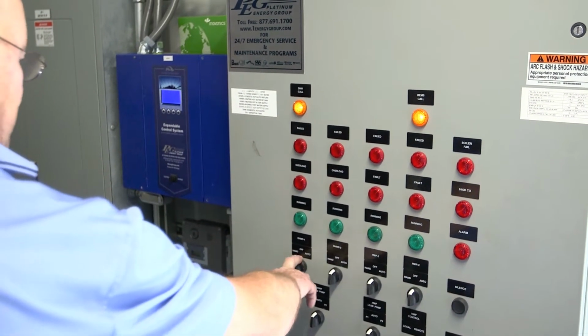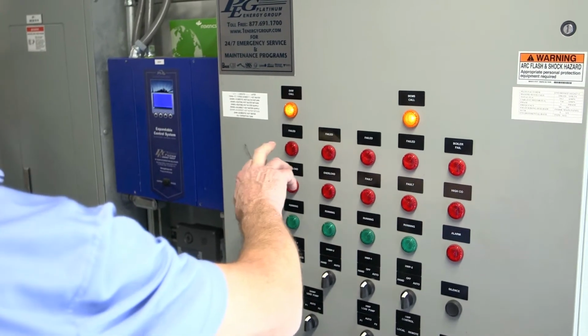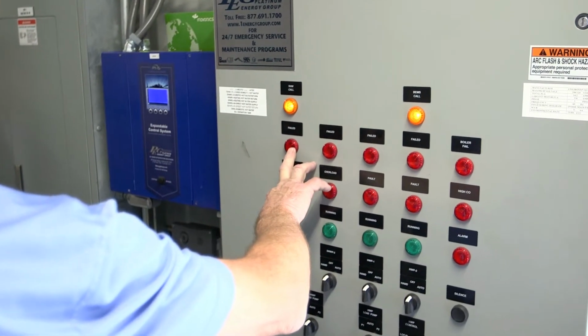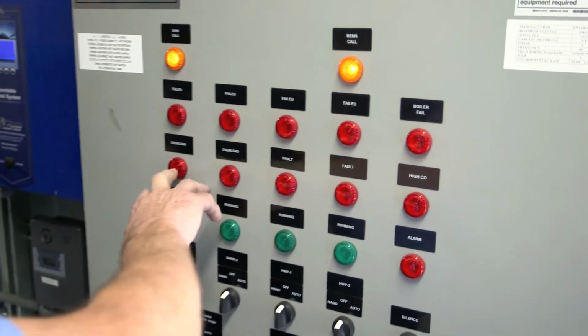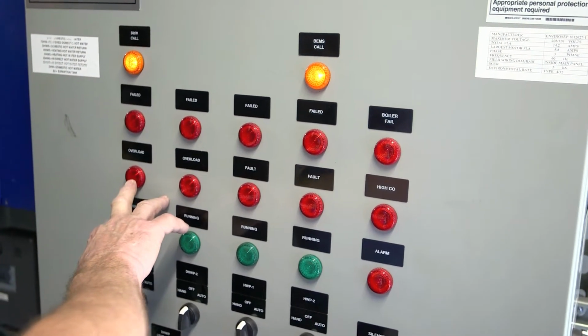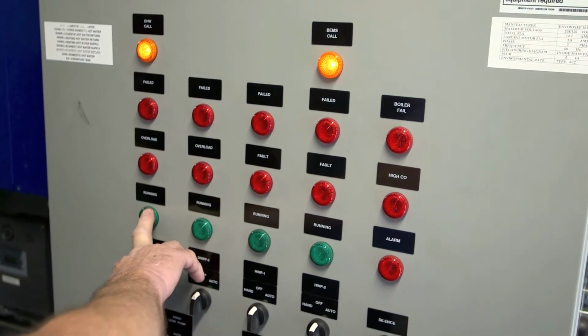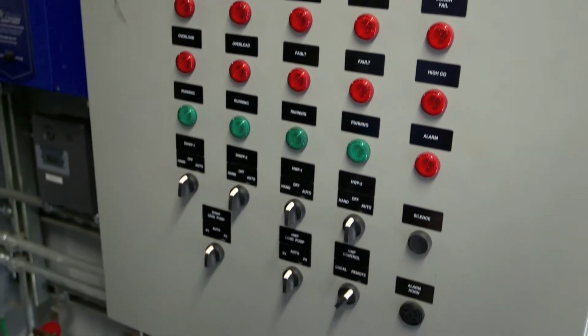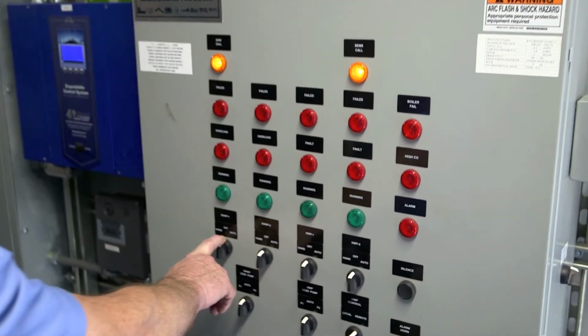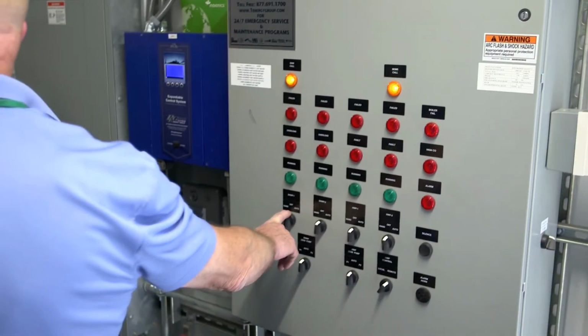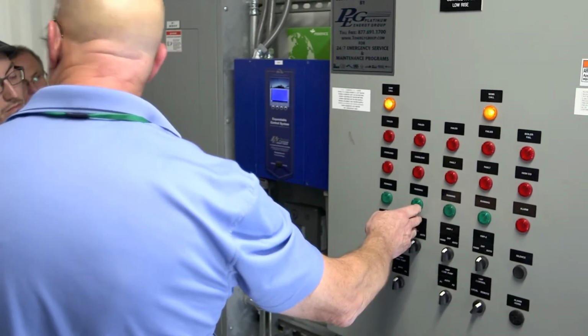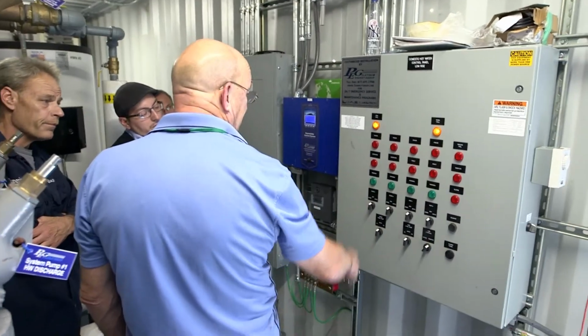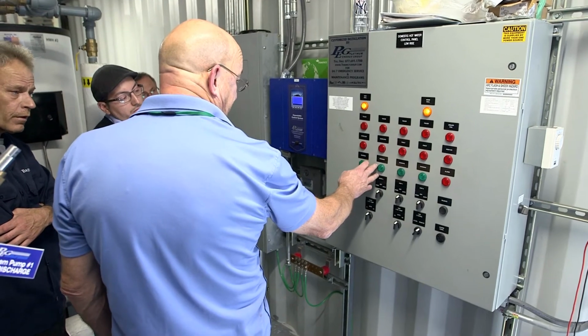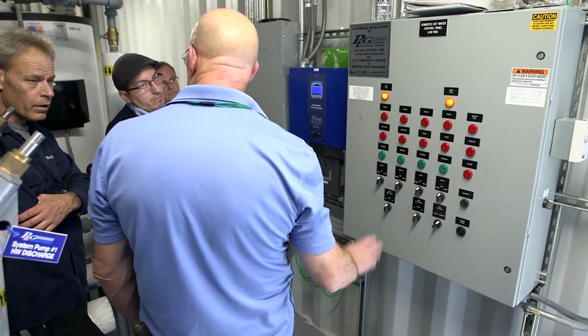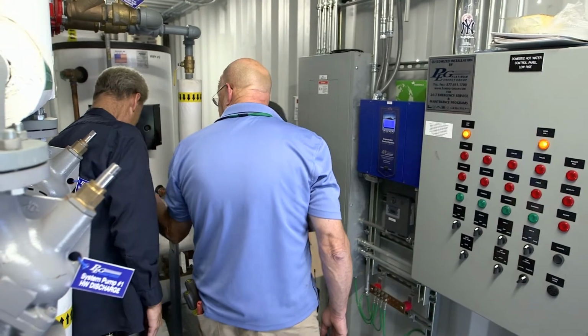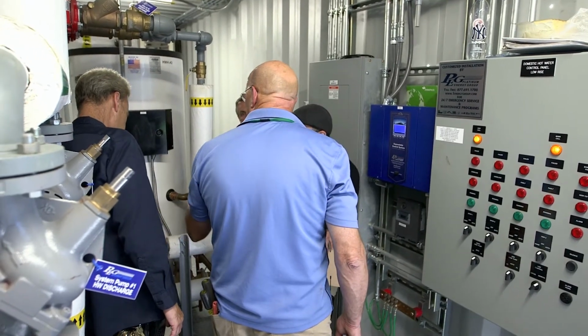We'll take this one for example. This is domestic hot water pump number 1. It tells you come in here, it's failed, something's wrong with the pump, all right? It's an overload, short circuit somewhere, all right? So this pump's not going to run. And green is running, tells you it's running, all right? You can turn the pump off here, okay, to off, so isolate that pump so it only runs on the one set of pumps. All right? When this comes on, either one of these, domestic hot water pump 1 or 2, domestic hot water pump 1 and 2 is both pumps for tank number 1 and both pumps for number 2.